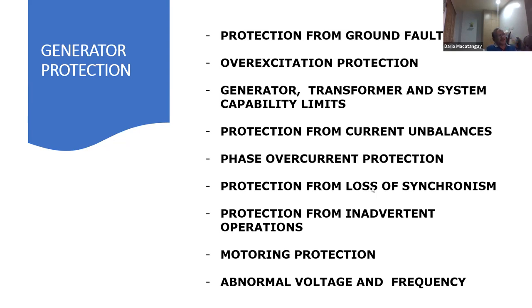Motoring protection is actually a reverse power protection. Motoring power protection happens when you lose the prime mover input. You have the turbine input to the generator, and then suddenly you lose the turbine. The generator cannot, of course, stop. It will continue to rotate, so it's going to be motoring. It's going to drive the turbine, and the system will power it. So with motoring protection, you need to trip the generator from reverse power.